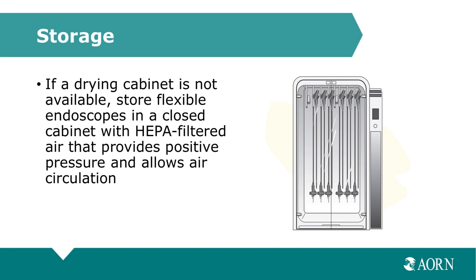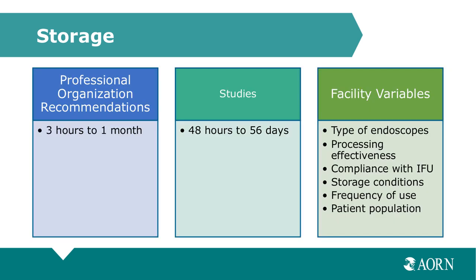Now, if a drying cabinet is not available, then your flexible endoscopes can be stored in a closed cabinet with HEPA-filtered air that provides positive pressure within the cabinet and allows air circulation around the flexible endoscopes. Now, the evidence regarding the maximum safe storage time for processed endoscopes is inconclusive, and we looked at recommendations from professional organizations and found that the maximum storage times recommended by these organizations were not in agreement, and they ranged anywhere from 3 hours to 1 month.